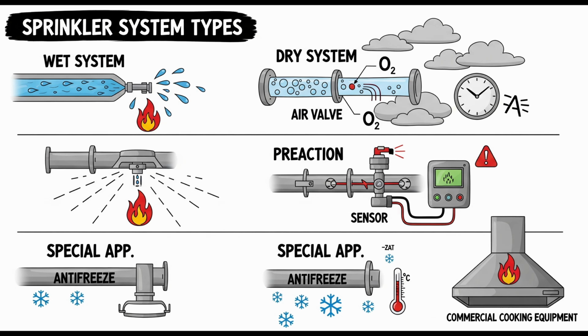Pressure gauges are required again above and below pre-action valves, just below deluge valves, and on the air supply line if one is used for supervision. Standard procedure, checking pressure at key points. Yep, monitoring system status. A supply of spare fusible elements, at least 2 of each temperature rating used in the system, must be kept on the premises. For replacing activated detectors or sprinklers.